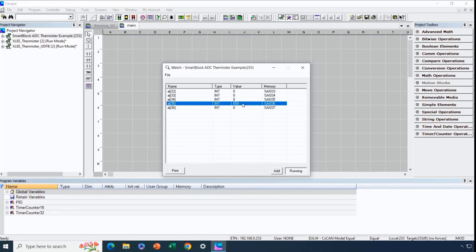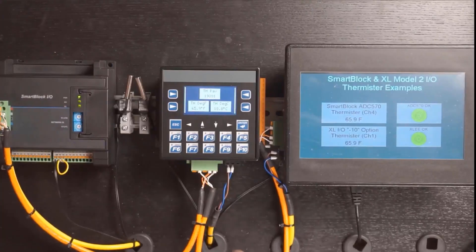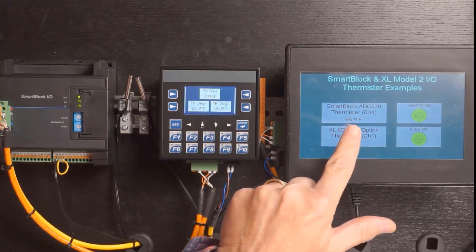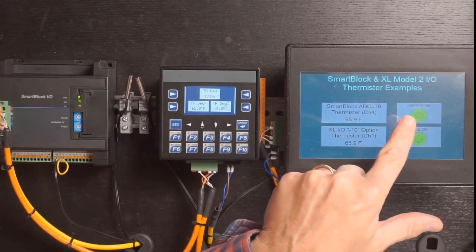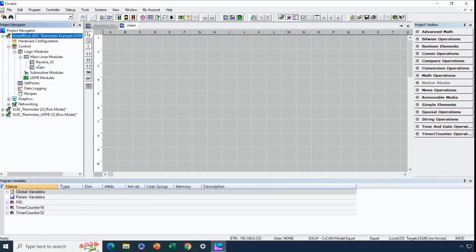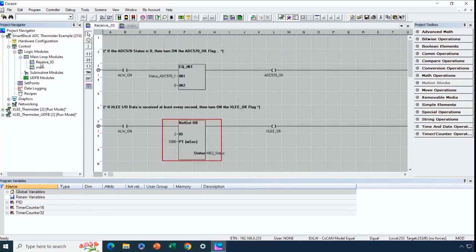It also shows how AI35 as a real-world I/O array in variable-based advanced ladder correlates to %AI36 for actual memory addresses. We can see the data reported by the smart block at 65.9 degrees Fahrenheit, and there's an ADC570 OK LED on the screen. Under the Receive I/O section, we created a single rung that monitors the status register of the smart block and assigned a status variable to it. If it has a value of zero, we know everything is good and we can turn on our OK indicator. That's what's involved in using the ADC570 or ADC970 smart block modules for thermistor inputs.